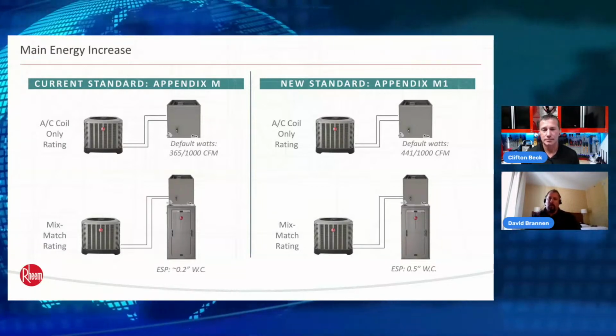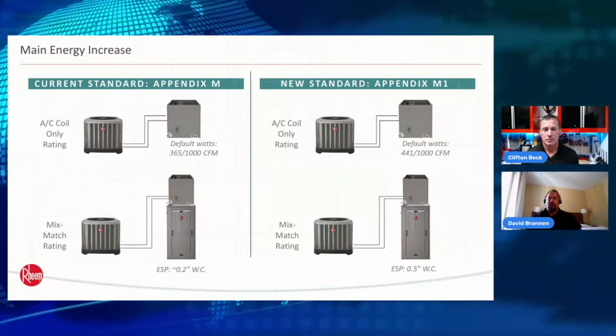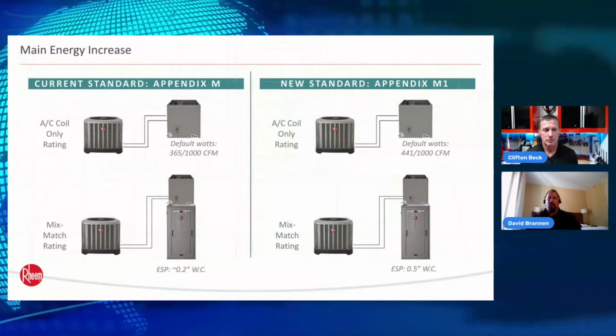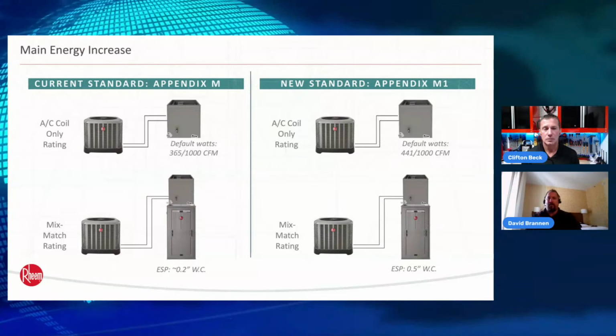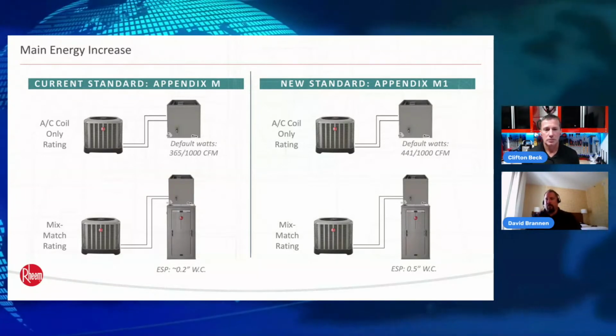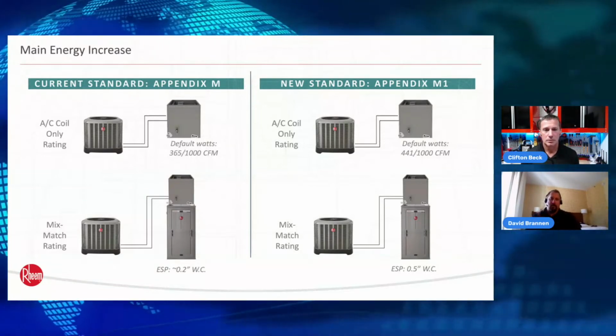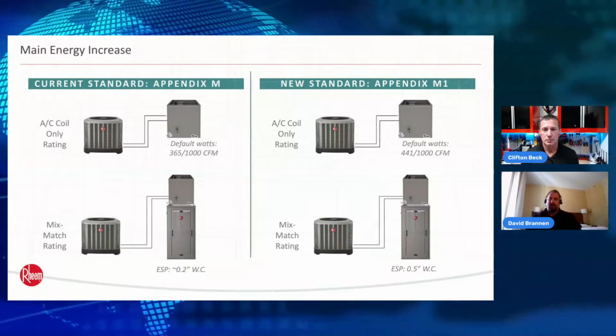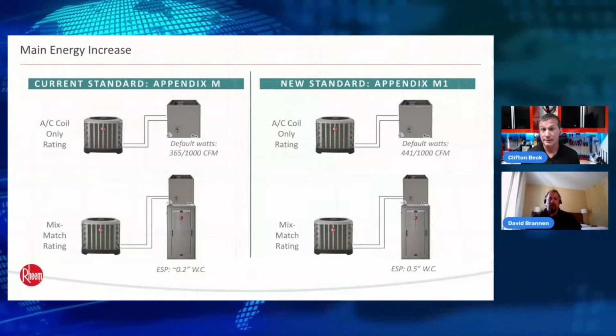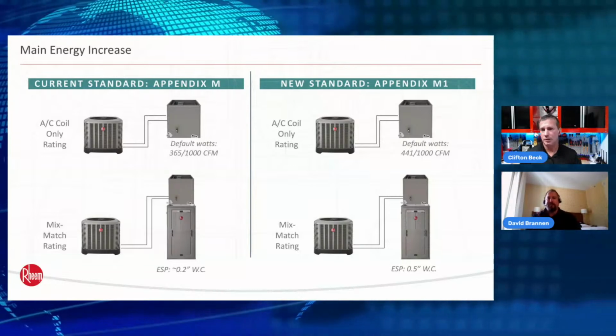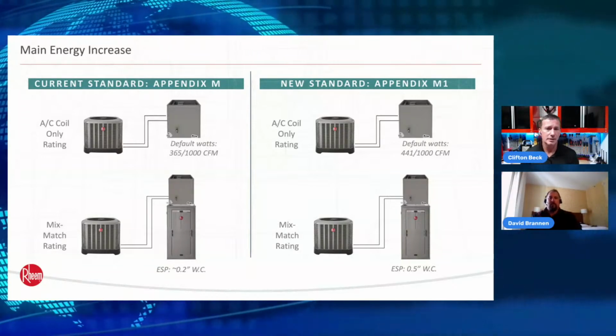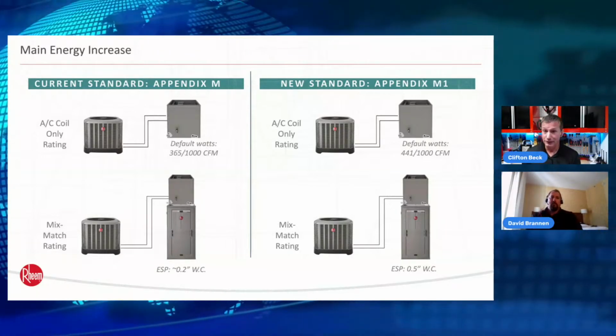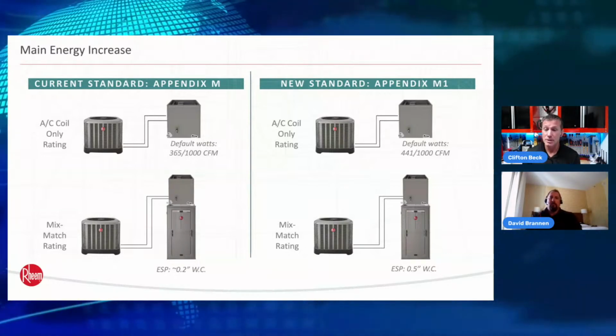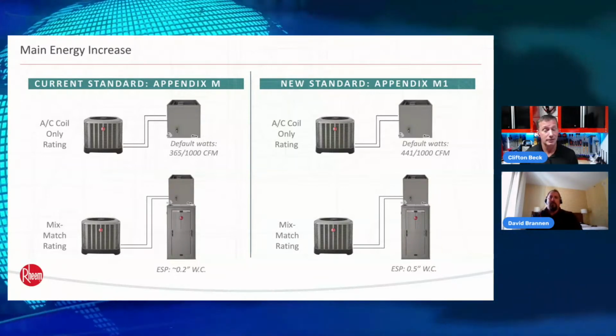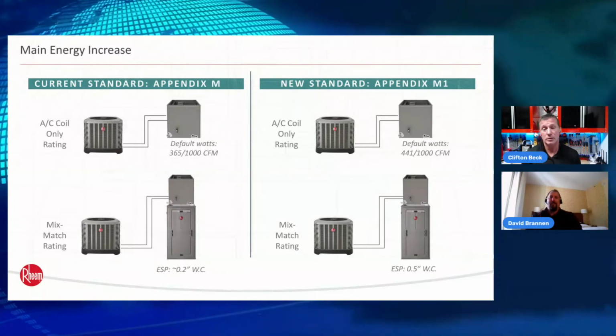So we're going from 365 watts per thousand CFM to 441 watts per thousand CFM, and a total external static from 0.2 to a total external of 0.5, which realistically is still more realistic, lower than what we see. Yeah, absolutely. I've always said in our industry, 0.5 is difficult in the Midwest. There are many places in the country where 0.5 is rarely realistic, even on brand new construction.